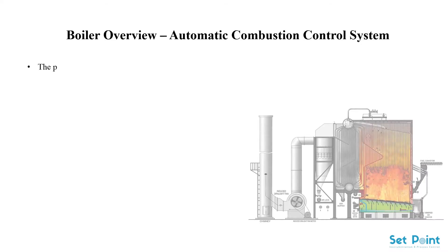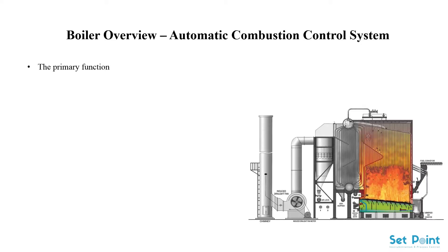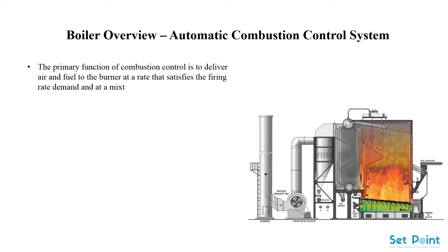In this tutorial, I would like to talk about the automatic combustion control system used in the industrial boiler. The primary function of combustion control is to deliver air and fuel to the burner at a rate that satisfies the firing rate demand and at a mixture air-fuel ratio that provides safe and efficient combustion.